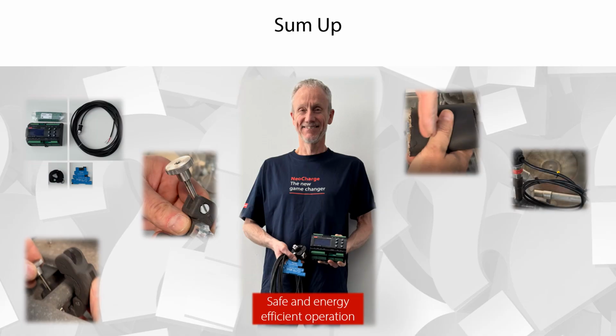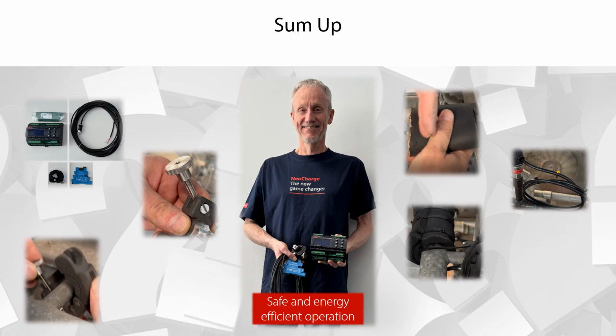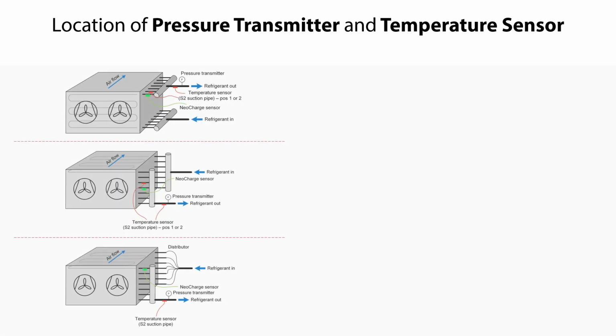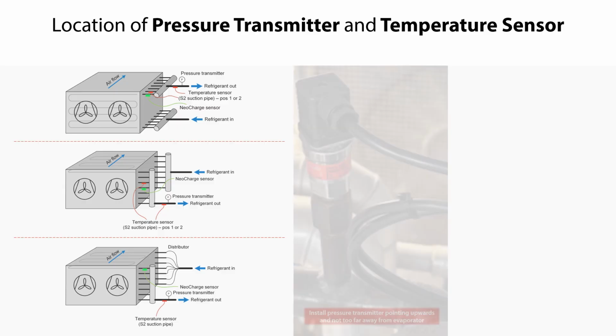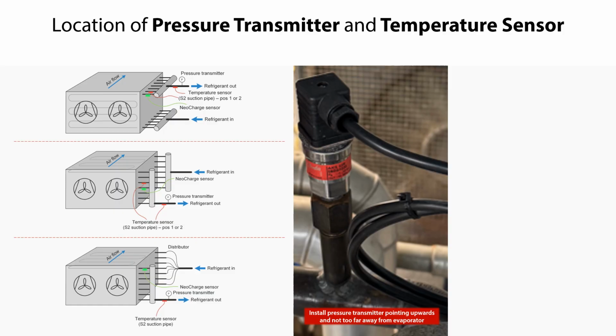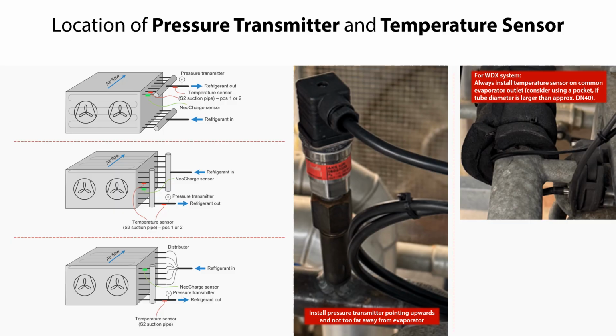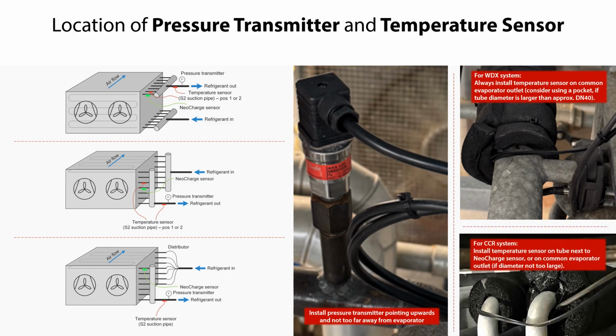So, let us then look at how to locate and orient the pressure transmitter and temperature sensor, and finally, where to find information about the Neocharge electrical installation. The pressure transmitter and temperature sensor are accessories and they are used for standard superheat measurement. We recommend that the pressure transmitter is installed so that it is pointing upwards as seen here in this example. It is important that the pressure transmitter is not installed too far away from the evaporator due to pressure drop in the suction line. For a WDX system, you should always install the temperature sensor on the common evaporator outlet tube. Consider using a pocket if the tube diameter is larger than approximately DN40. For a CCR system, you can install the temperature sensor on the evaporator tube next to the Neocharge sensor, or on the common evaporator outlet tube if the diameter is not too large.